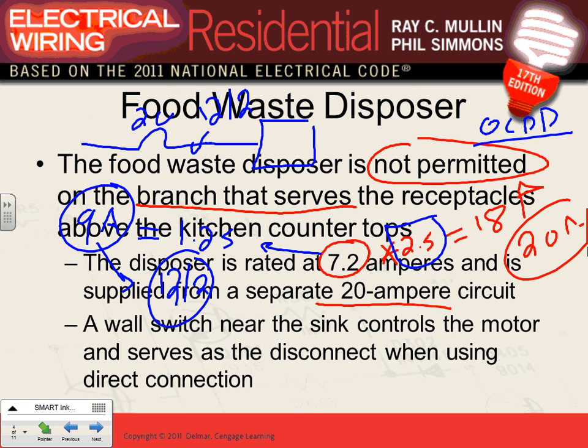Now, the second thing I want to highlight, they have a wall switch near the sink. I hope you guys did it. Jeff, I think you guys did that one. You put a wall switch for the garbage disposal. That wall switch has two functions. If you hardwire the equipment, it acts as your disconnect, and also your controller, to turn it on and off. So two functions for the snap switch, typically with these. Either controller, turn it on and off, and also disconnect if it's hardwired.